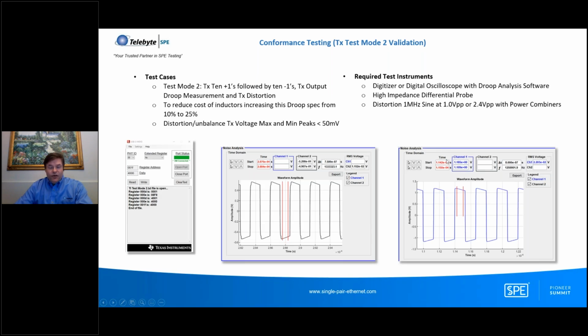Now, with the distortion test, since we have power on the same data pair, there's power coupling and voltage limiting circuits combined on this pair, and what we don't want is a DC unbalance. So there's data encoding on the 10BASE-T1L signal to try to minimize any DC bias. We mix in a 1 megahertz sine wave at 1 volt, or 2.4 volts depending on your operating mode. Then we look over 10 milliseconds and make sure that the peaks are the same value as the minus peaks within 50 millivolts. So that's the test that we run in test mode 2.